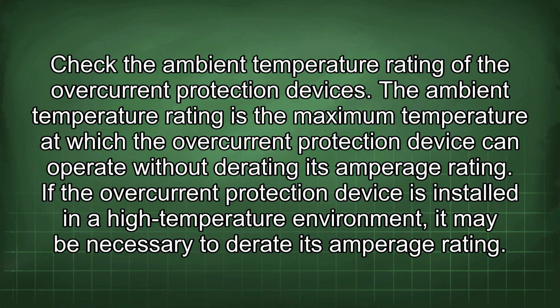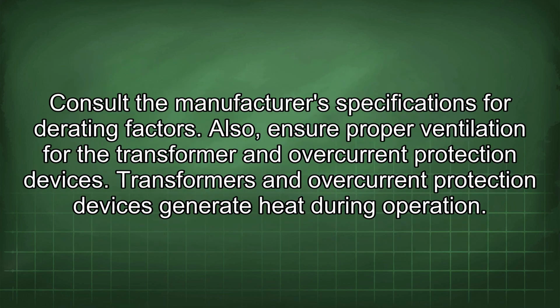The ambient temperature rating is the maximum temperature at which the overcurrent protection device can operate without derating its amperage rating. If the overcurrent protection device is installed in a high-temperature environment, it may be necessary to derate its amperage rating. Consult the manufacturer's specifications for derating factors.